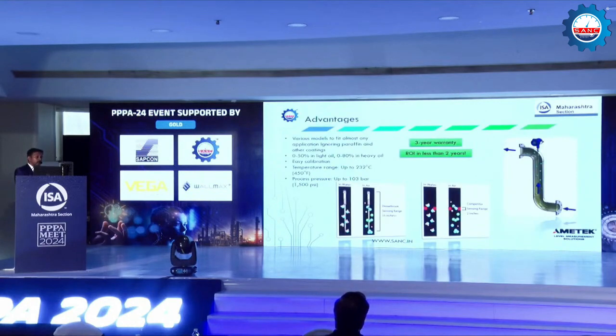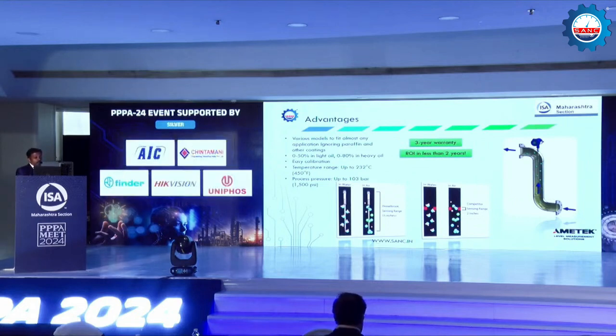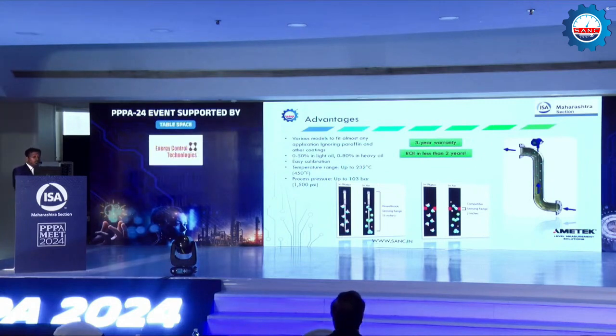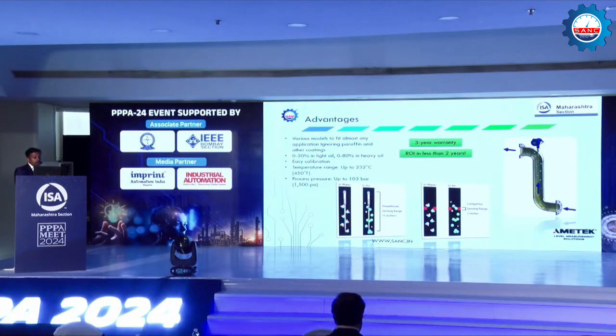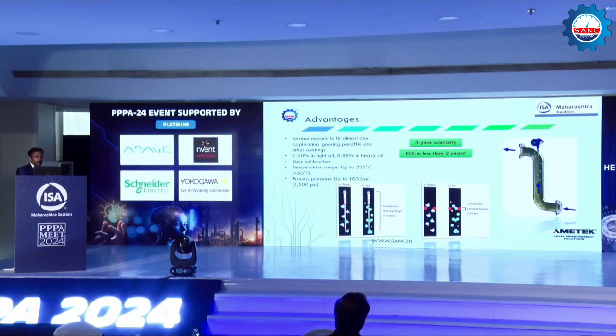The advantage of having RF admittance for water measurement in oil is that you get a larger measuring area, whereas other technologies available for measuring water content are microwave and some spectroscopy technologies. Compared to that, we have a larger sampling area, and it is online, continuously monitoring when the oil is flowing. It's not a sampling method where we take out a sample and check the water content for a particular batch. It is online. So that is one advantage. And high temperature rating, and we have a 3-year warranty for this product. And one of the clients in USA told us that they got their return on investment in 2 years.